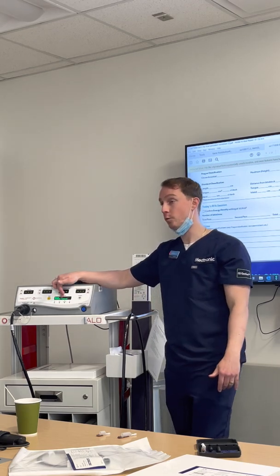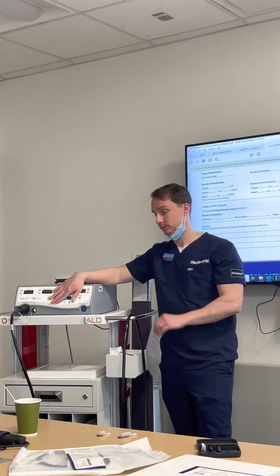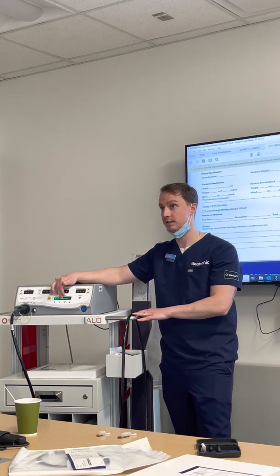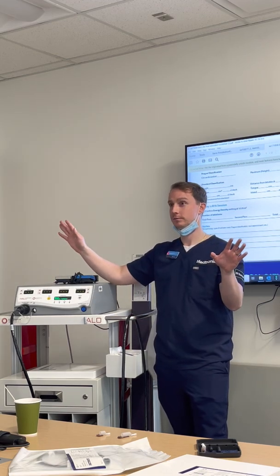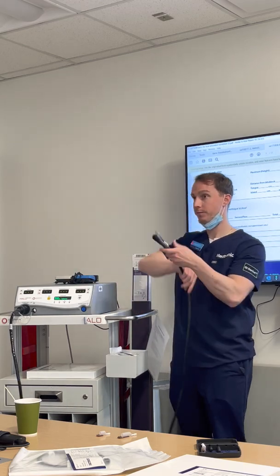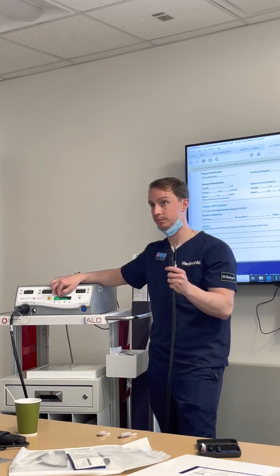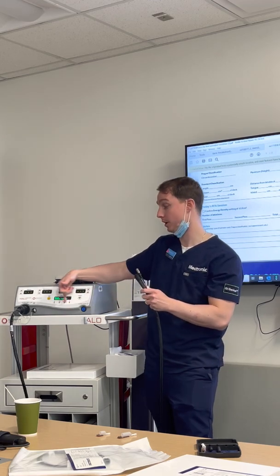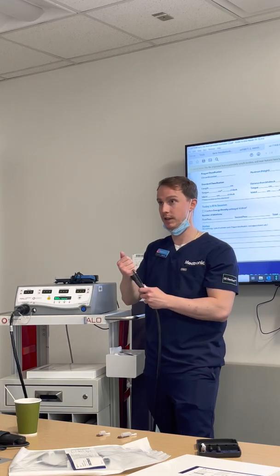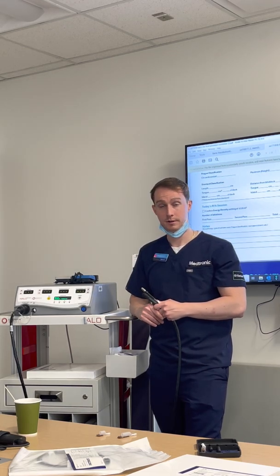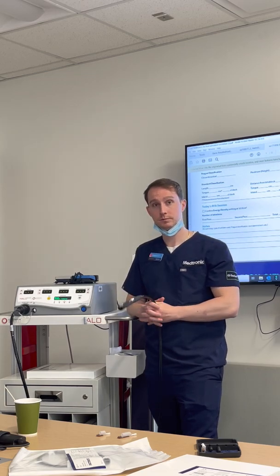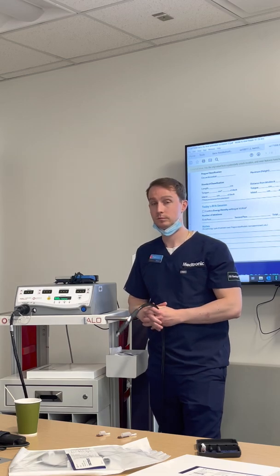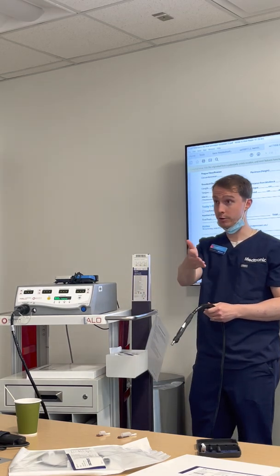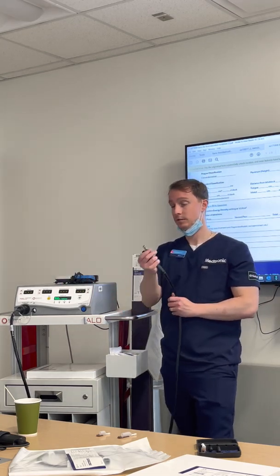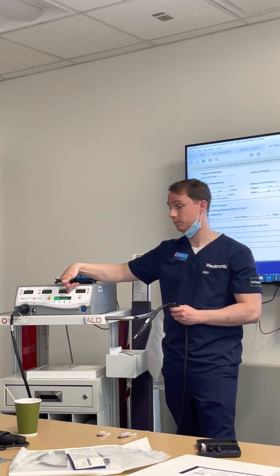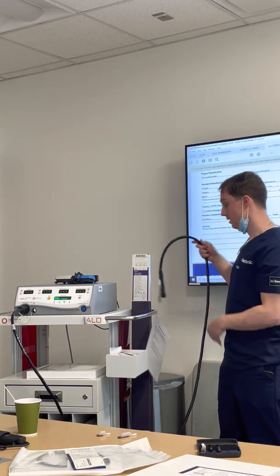If we disconnect the catheter before we look at this screen and see the total number of ablations, that number is gone forever. So before we disconnect the focal catheter from the cord, make sure we write the total ablations down. If we disconnect at the end of the procedure and forget, that number is gone. If we reconnect that catheter, that total number doesn't exist. Also, we need to document in Epic in the procedure notes how many ablations we do. So that's another reason to be super cognizant not to disconnect the catheter before we note how many ablations there are.